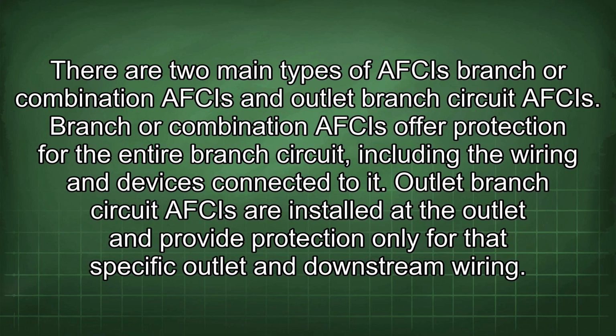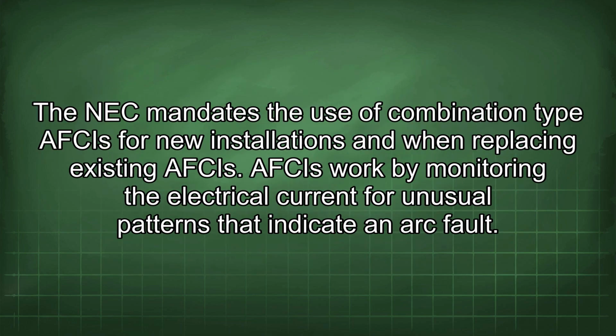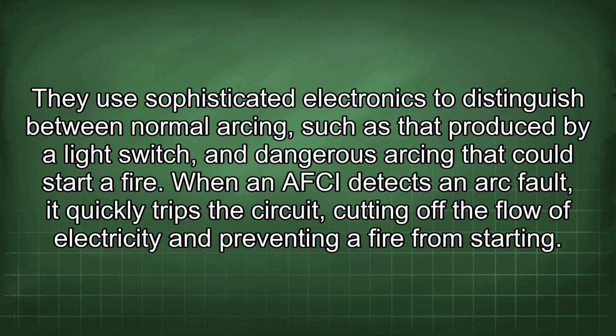Branch or combination AFCIs offer protection for the entire branch circuit, including the wiring and devices connected to it. Outlet branch circuit AFCIs are installed at the outlet and provide protection only for that specific outlet and downstream wiring. The NEC mandates the use of combination type AFCIs for new installations and when replacing existing AFCIs. AFCIs work by monitoring the electrical current for unusual patterns that indicate an arc fault. They use sophisticated electronics to distinguish between normal arcing, such as that produced by a light switch, and dangerous arcing that could start a fire.